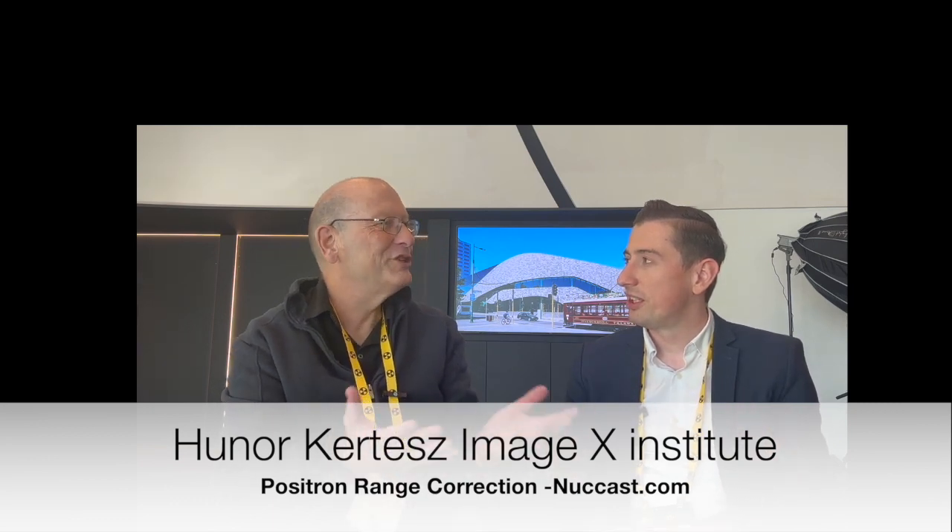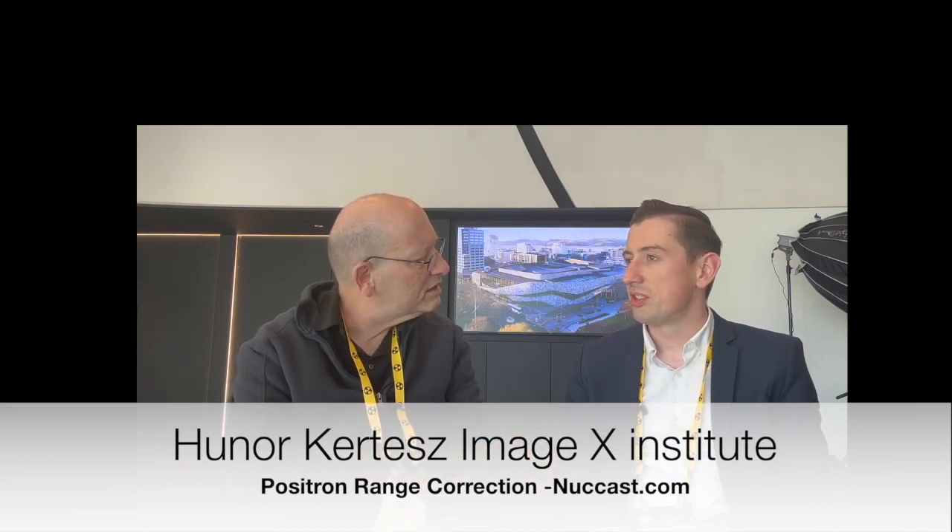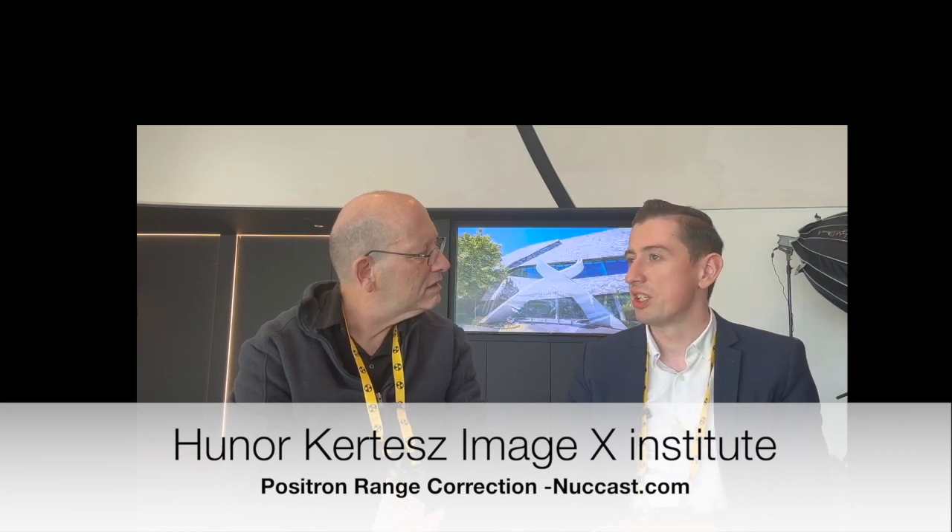This is an issue because it reduces the resolution of your image. Fluorine-18 is a couple of millimetres — one or two millimetres — so for F-18 it's not a major issue relative to current system resolution. However, for Gallium-68, Iodine-124, or Rubidium-82, which has the highest positron range, the maximum within lung tissue can go up to 30 millimetres for Gallium-68.